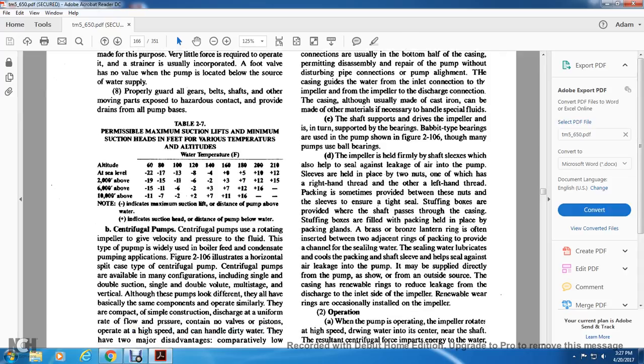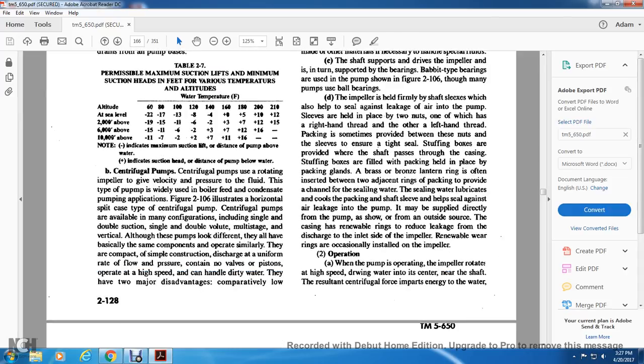Alright, centrifugal pumps. Centrifugal pumps rotate an impeller to give velocity and pressure to the fluid. This type of pump is widely used for boiler feed and condensate service. Figure 2-106 illustrates the horizontal split case type of centrifugal pump. Centrifugal pumps are available in many configurations, including single and double suction, single and double volute, and multiple stage vertical. Although these pumps look different, they all have basically the same components operating similarly. They are compact with a simple construction, discharge at a uniform rate of flow and pressure, and contain no valves.